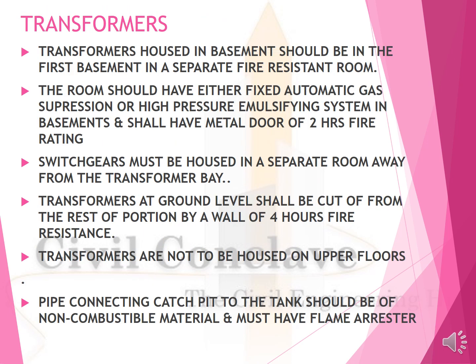Transformers. A transformer housed in a basement should be in the first basement in a separate fire resistant room. The room should have fixed automatic gas suppression and a metal door of 2 hours fire rating. Switch gears must be housed in a separate room away from the transformer bay. A transformer at ground level shall be cut off from the rest of the portion by a wall of 4 hours fire resistance. Transformers are not to be housed in the upper floor. The pipe connecting the catch pit to the tank should be of non-combustible material.